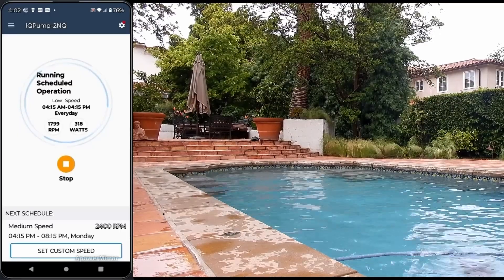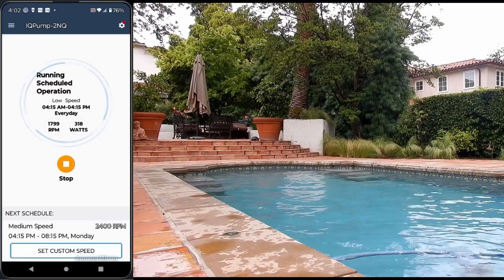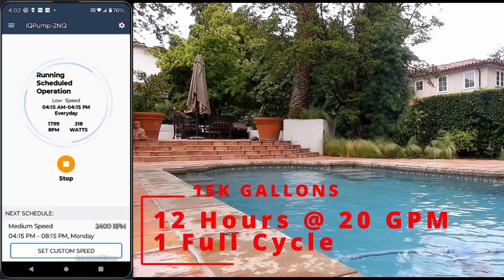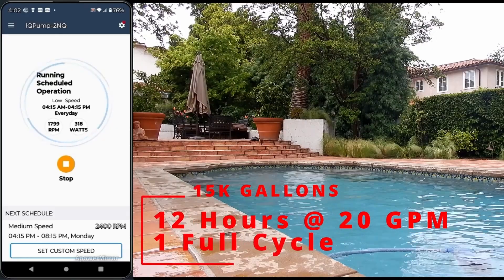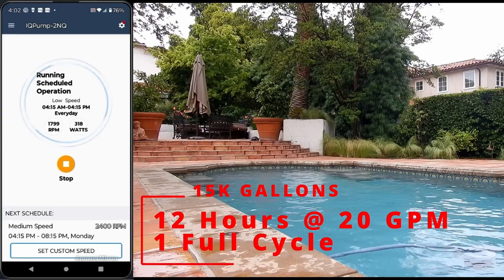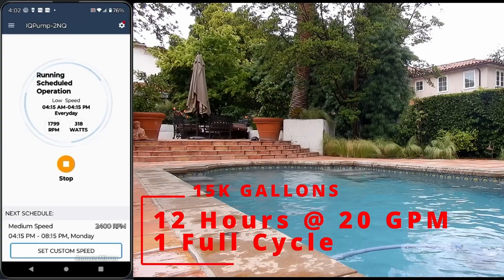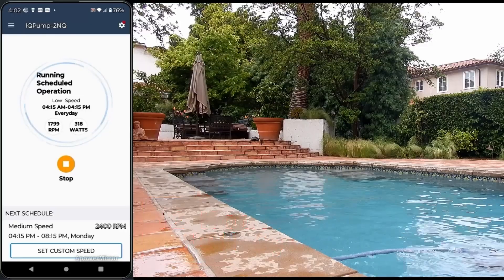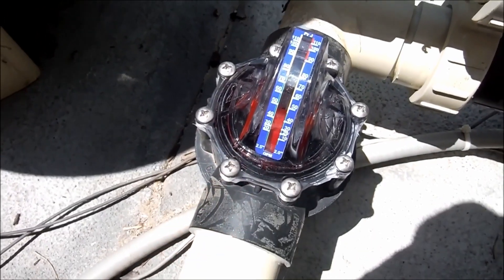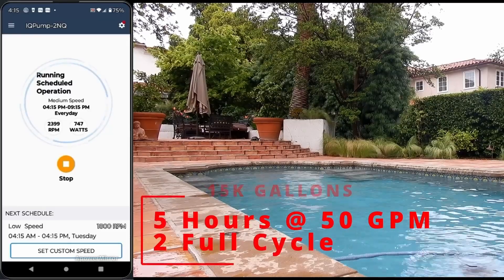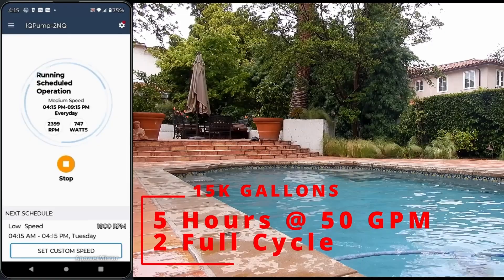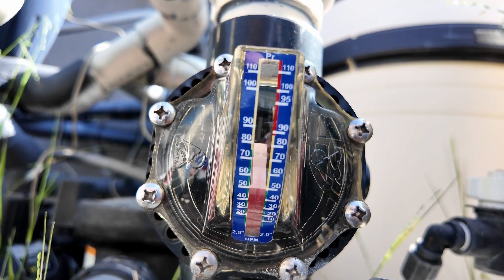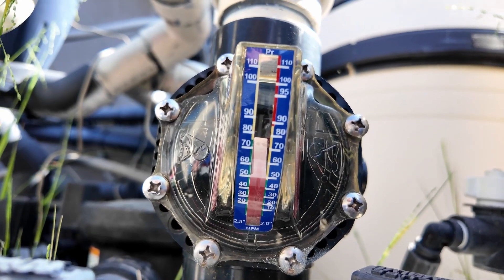Here's an example of an ideal runtime that will also save you the most energy. This pool is 15,000 gallons. I'm going to run the low speed at 1,800 RPMs for 12 hours, which gives one full cycle of water at 20 gallons per minute. Then I'm going to run a medium speed of 2,400 RPMs for five hours, which is 50 gallons per minute, giving me the second cycle of water.